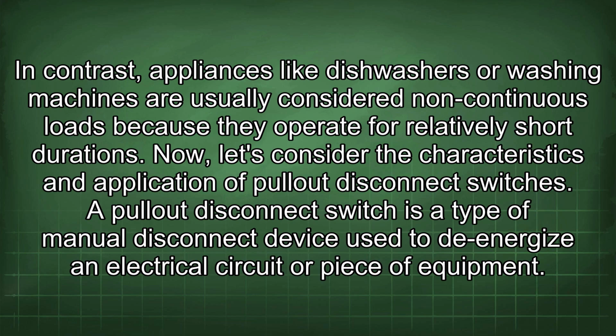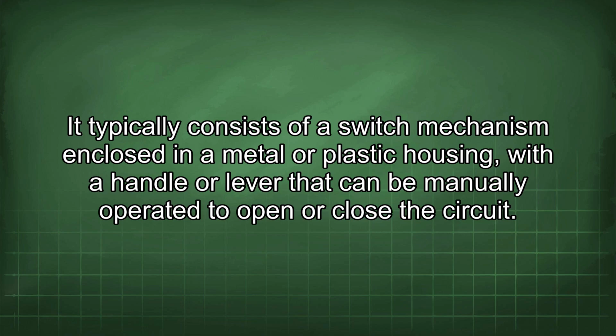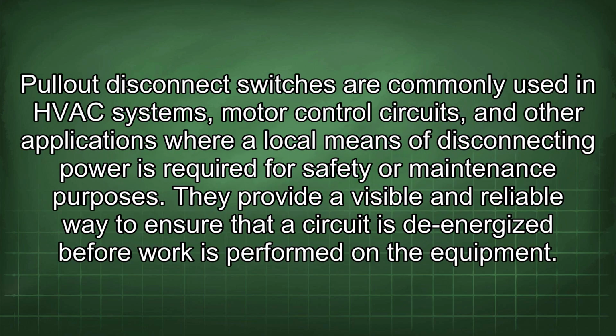Now, let's consider the characteristics and the application of pullout disconnect switches. A pullout disconnect switch is a type of manual disconnect device used to de-energize an electrical circuit or piece of equipment. It typically consists of a switch mechanism enclosed in a metal or plastic housing, with a handle or lever that can be manually operated to open or close the circuit. Pullout disconnect switches are commonly used in HVAC systems, motor control circuits, and other applications where a local means of disconnecting power is required for safety or maintenance purposes.